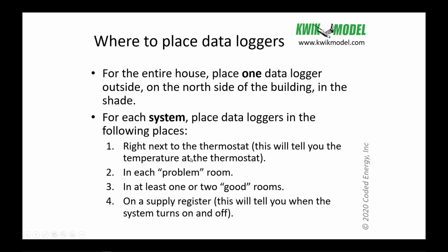Okay. Where do I put those in a house? Well, I put one right next to the thermostat. What that does is it tells me the temperature at the thermostat, okay? And then I ask the homeowner, what rooms are your problem rooms? Which rooms are you complaining about? And I'll put a data logger in each of those problem rooms. But it's also important to ask them, when these rooms are not comfortable, what rooms are comfortable? What are your most comfortable rooms in your house when the other rooms are not comfortable? And then I'll put a data logger in those as well.